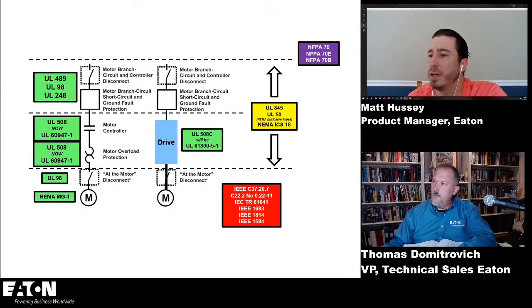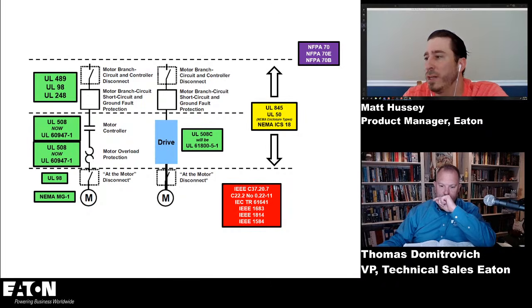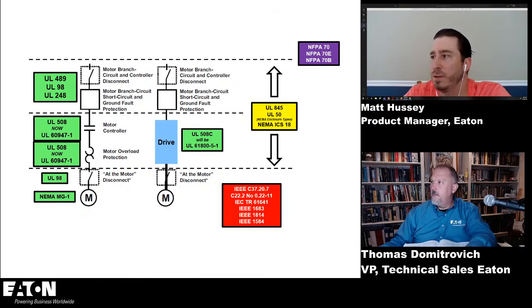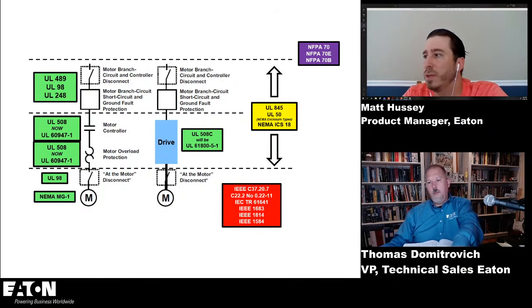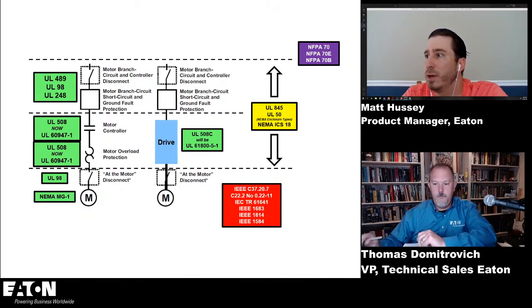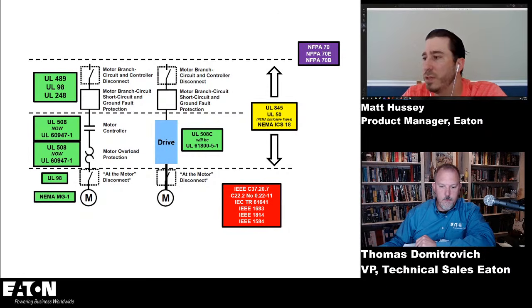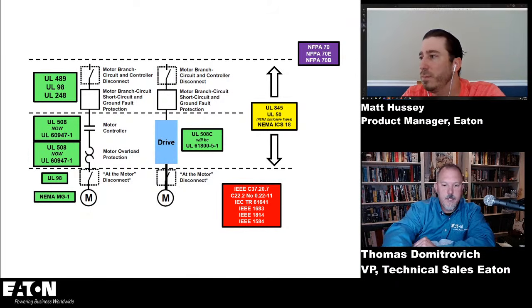So I was trying to get a good visual showing all the standards for the disconnects, the overcurrent protective devices, the contactors, the overloads, and how those devices are tested and built out. It provided a lot of good guidance for me to understand as well. We've got other installation codes, like the National Electric Code, 70E, electrical safety in the workplace, and NFPA 70B, how equipment should be maintained. And then we've got some other standards listed below there in the IEEE, where we're doing a lot more from electrical safety and whatnot.